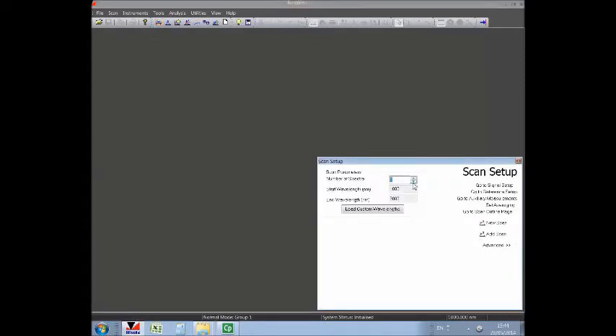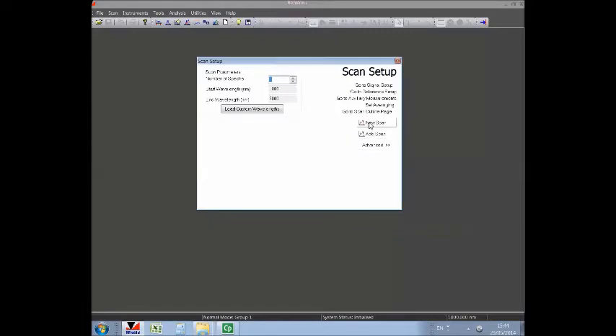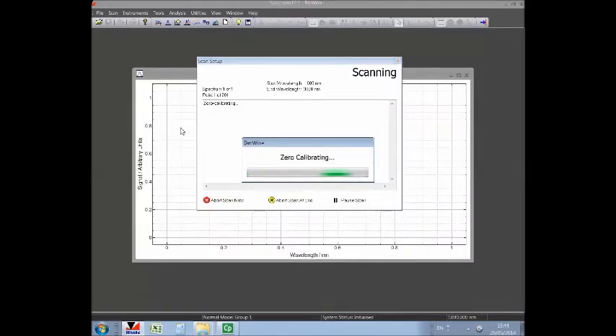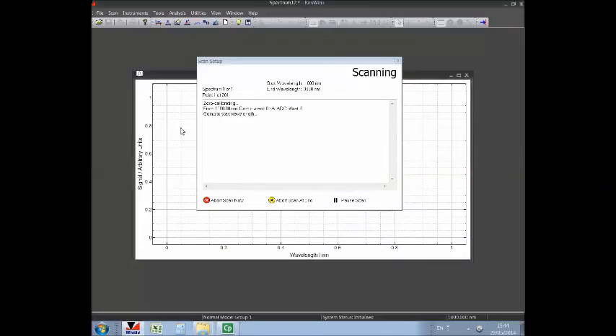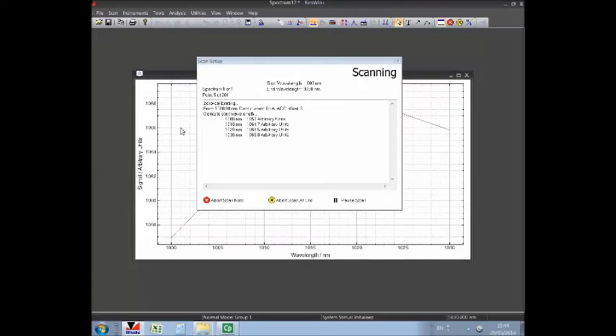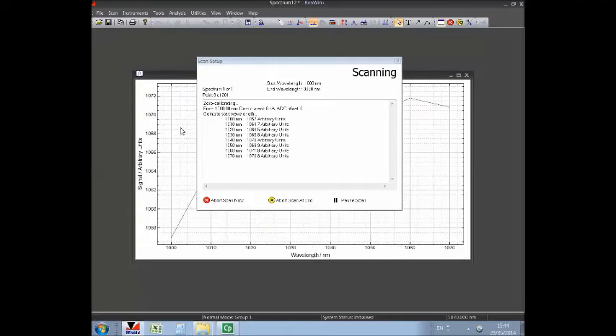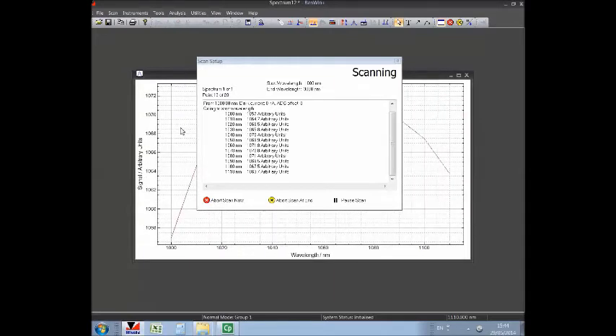I will perform one single scan. Hitting new scan, we see that the y-axis has signal in arbitrary units, in the same manner that we have done in the spectral check configuration. This is just to avoid confusion between this measurement and an absolute measurement. This is not an absolute measurement of irradiance of the source. This is just a relative spectral measurement. And we will look at the result when it is finished in a moment.